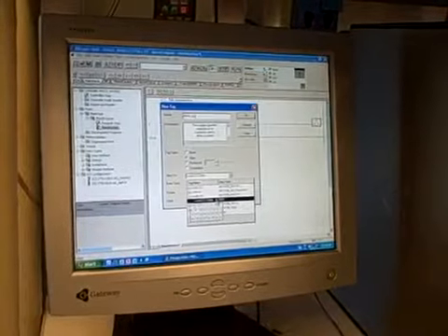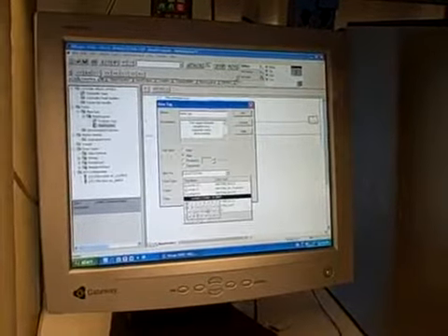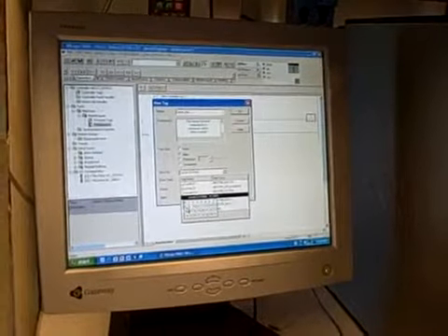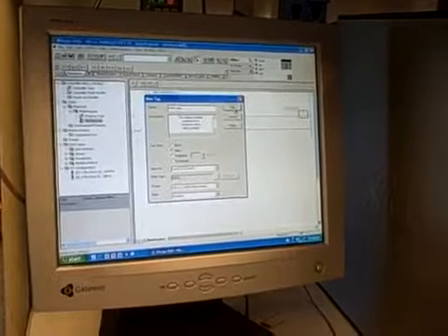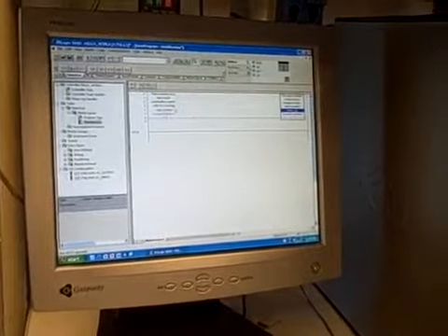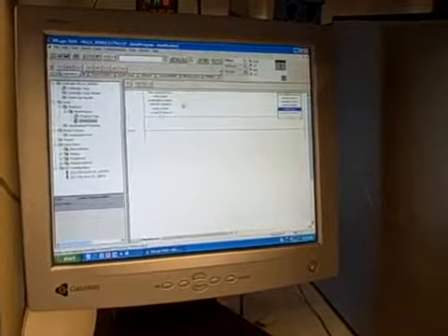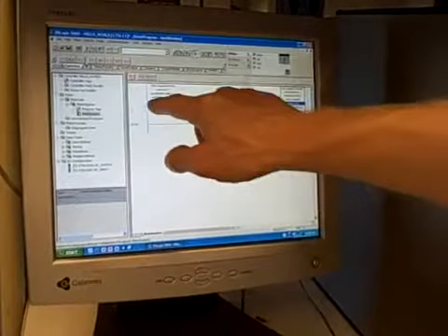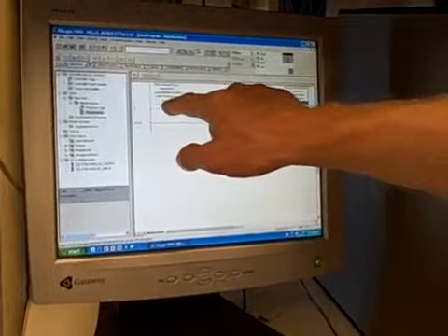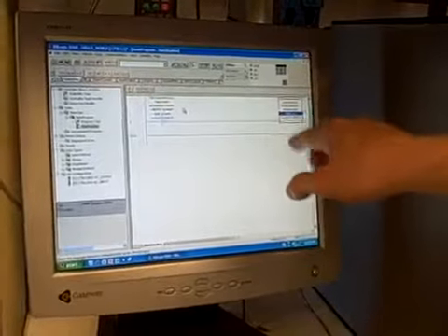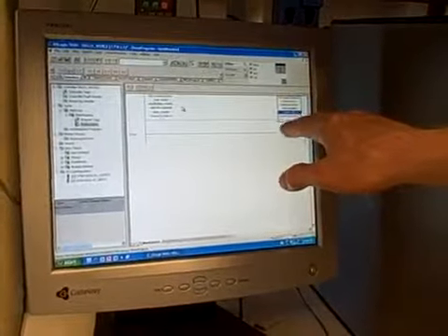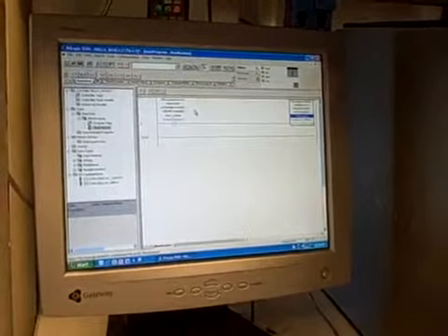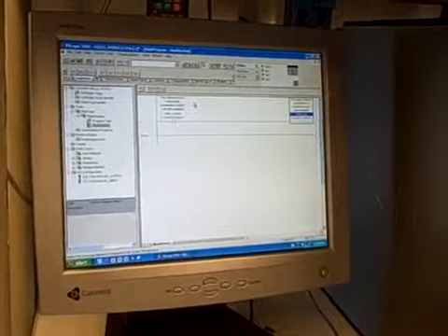Notice the pull-down menu that appears. I get to select the bit of this card, the particular channel on the output card that's going to be driven by that coil instruction. I'll select bit number 8 just for fun, and I'll click OK. So there we go. There's my simple program. I can do a syntax check, and it clears the check OK. So we're looking at an examine if closed instruction with the hardware address reference right there, my tag name, and the description. And then over here, a coil instruction, output enable coil, with hardware address reference, my tag name, and another description. Of course, at this point, I need to download this program to the controller.